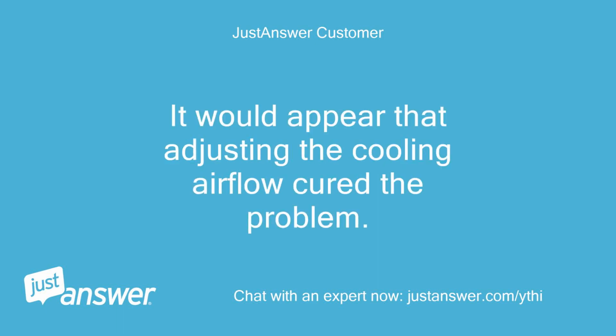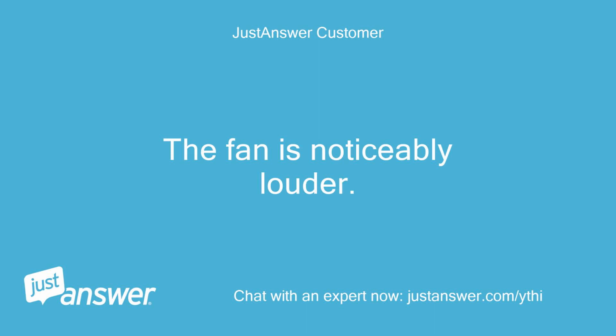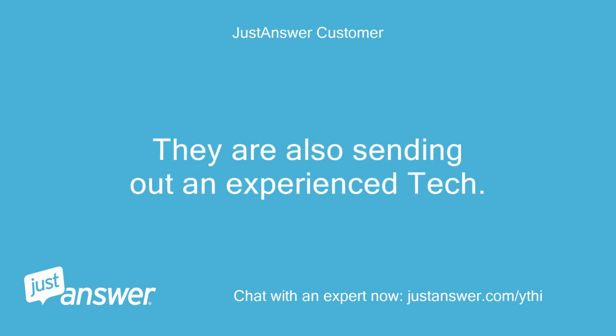It would appear that adjusting the cooling airflow cured the problem. The current DATS in Cool 1 is between 47.7 and 49.7 degrees. The fan is noticeably louder. Cool 2 kicks in without error and the DATS reading is around 55 degrees. The HVAC company has responded to my letter and will be refunding me the money I spent. They are also sending out an experienced tech.